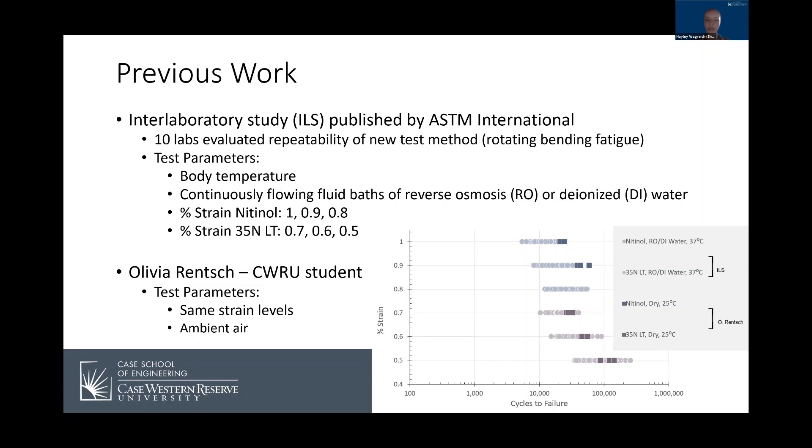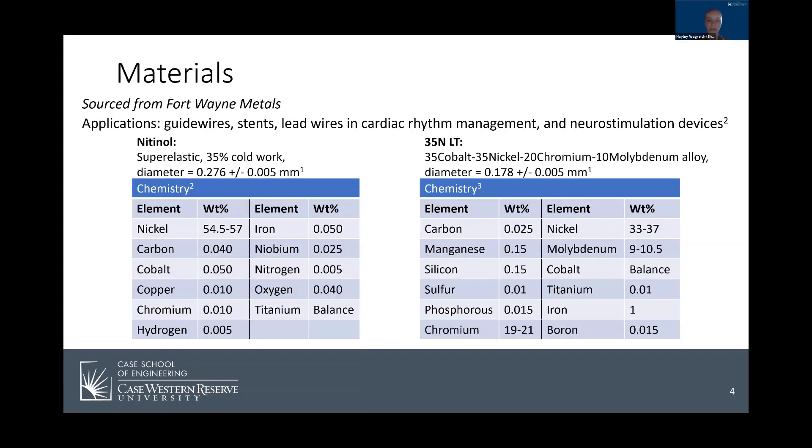The results are seen in this graph on the right where nitinol is in blue and 35N LT is in purple. The preliminary data shows that as the strain amplitude increases, the cycles to failure decreases. The two materials were sourced from Fort Wayne Metals and their chemistry and wire dimensions are included in these tables. The thing about the two materials that influences the results the most is their applications, which include many biomedical devices.